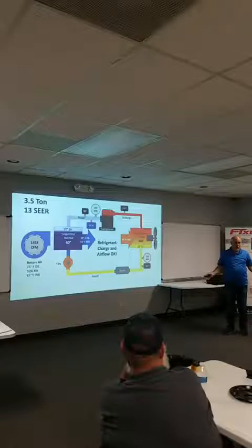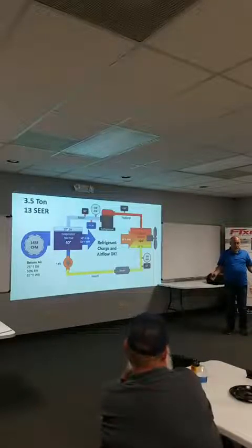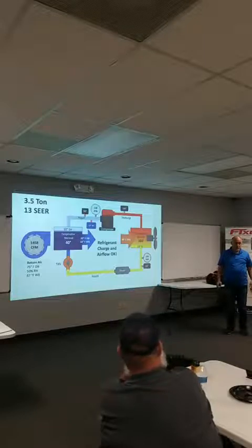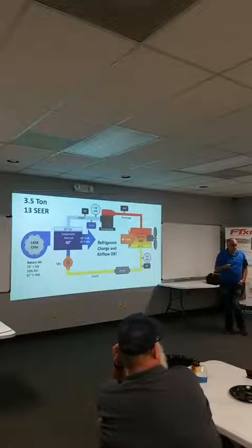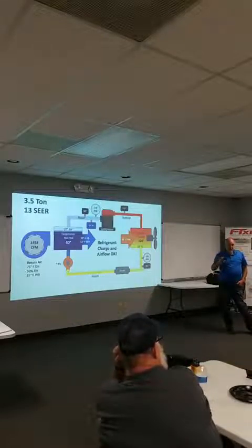Because there's gonna be a drop in suction pressure in that suction line because of the length of the suction line, right? Hopefully it's not more than 3 pounds. Hopefully somebody sized the line correctly, but that's not always the case. Even if it's insulated, if it's going through a hot attic or across a roof, it's gonna pick up additional superheat, right? Important thing to remember, the TXV cannot control superheat after the thermostatic expansion valve, right?